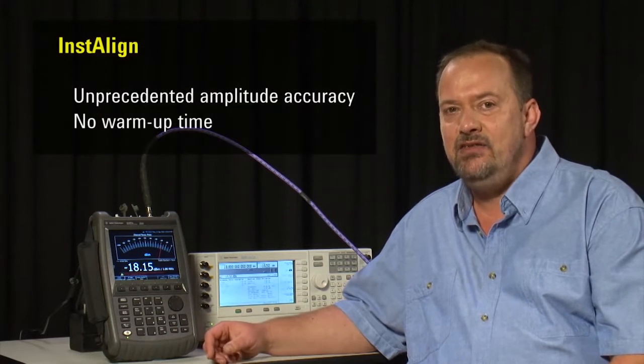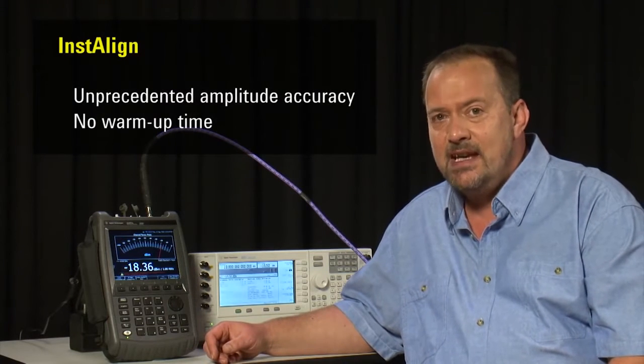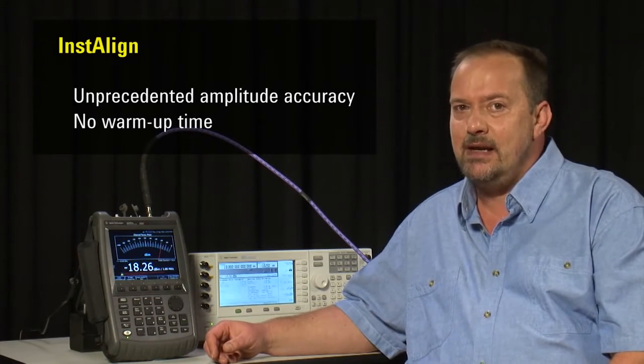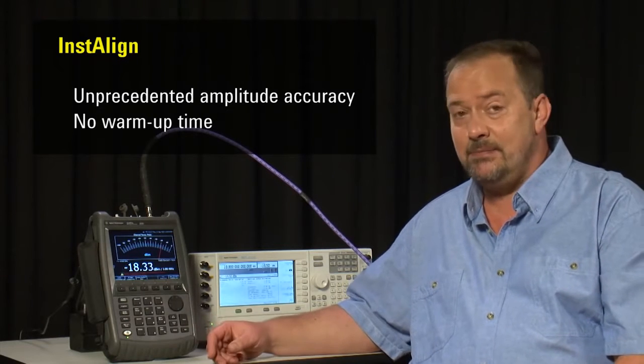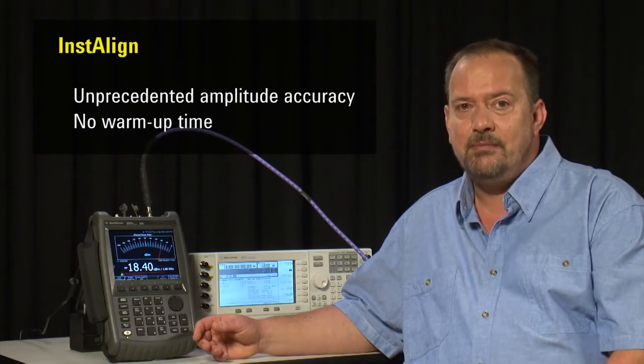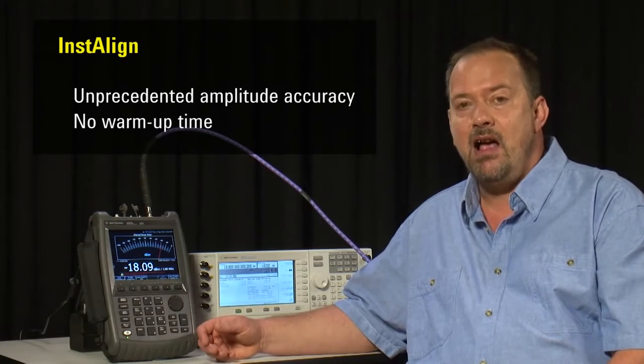This is made possible by Agilent's unique InstAlign technology, so that across the entire operating temperature range of the FieldFox, from minus 10 to plus 55 degrees centigrade, we can measure RF amplitude with a typical accuracy of about half a dB.